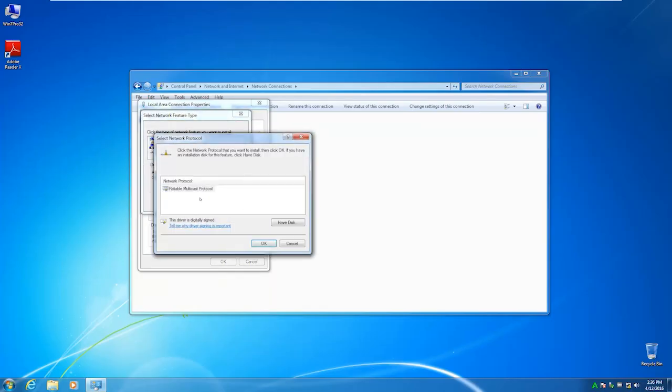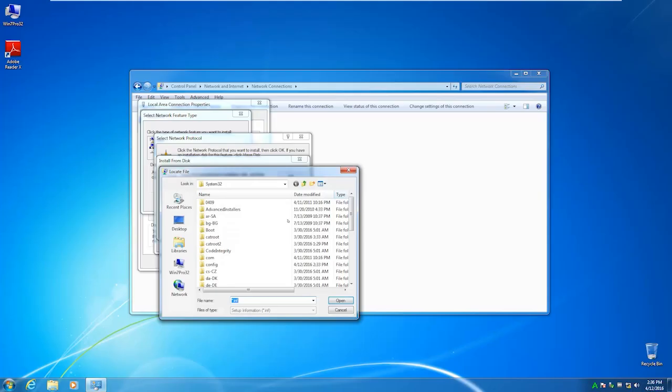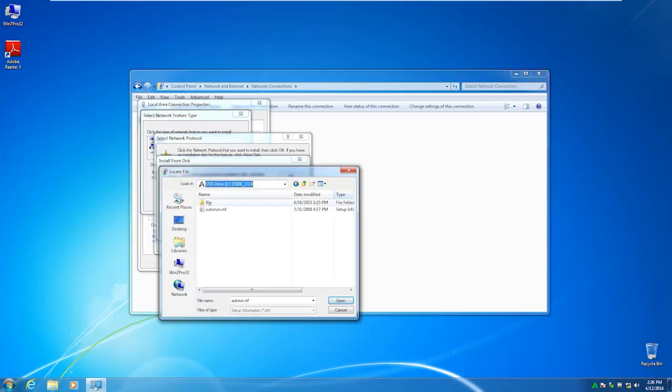Then click Have Disk. Click on the Browse button and go to your Genie 2000 CD /bin/G2K v3.4/AIM folder. In Genie 3.4, we added 64-bit support for the Snap driver as shown. Choose the appropriate folder for your type of system. For 64-bit systems, choose AIM SNAP6.INF, and for 32-bit systems, choose AIM SNAP5.INF. For this example, we will show the 32-bit installation.